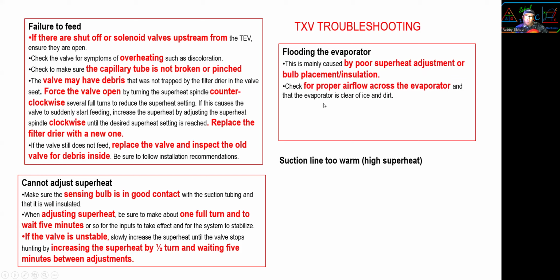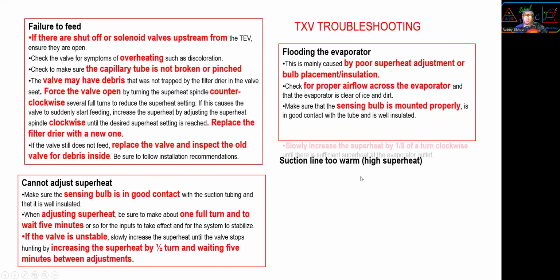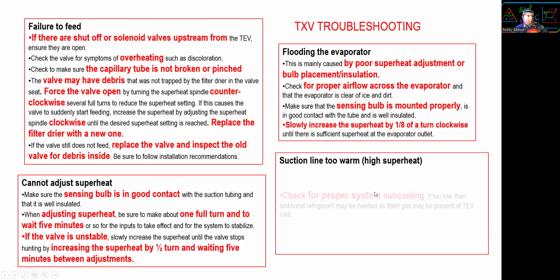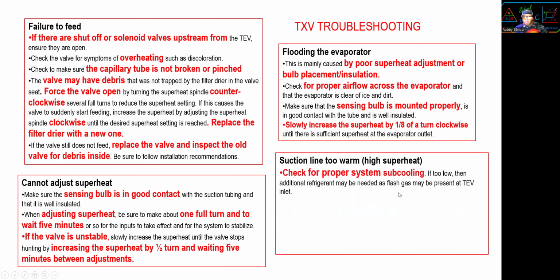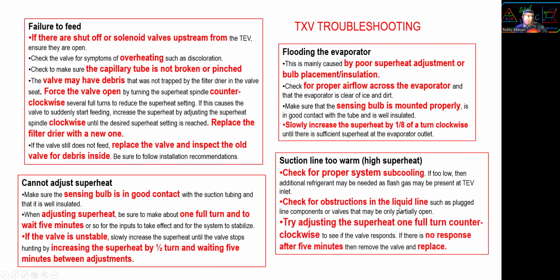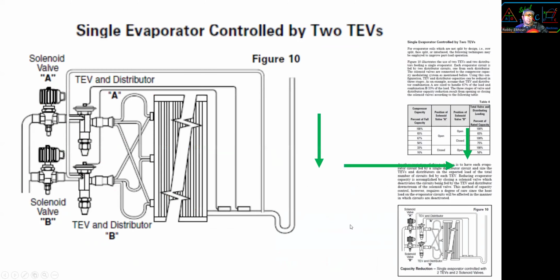For proper airflow across the evaporator, make sure it's not dirty. Make sure the sensing bulb is mounted properly, and increase by an eighth of a turn until significant superheat happens. Suction line too warm, check for proper system subcooling. Check for obstructed line in the liquid. Try adjusting superheat. Alrighty. It is very rare to adjust.